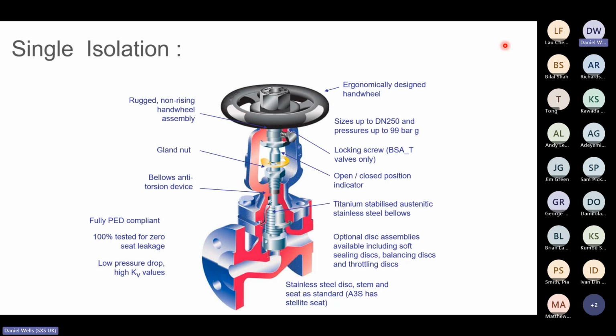That's spheroidal graphite iron. It stands up to water hammer a little bit better than cast iron. Better still, if we can move towards cast steel, that really is best practice. So the valve you can see on the screen, it's actually what we call a bellows sealed valve. Bellows sealed means we've eliminated the risk of any steam passing up the spindle, which could result in a nasty health and safety incident if and when those seals were to dry out and rupture.